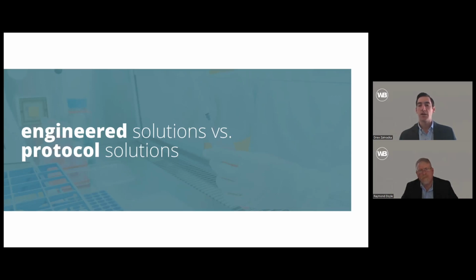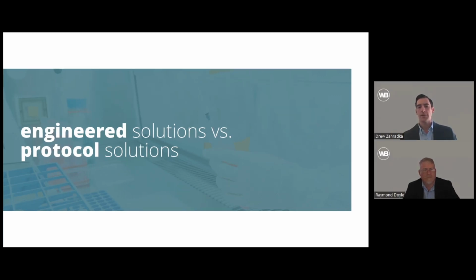So the engineered solution in this instance would have been to put in low wall returns, but low wall returns are not cheap. They require furring out the wall cavities so you can fit the duct, and it's more ductwork. Sometimes it has to be stainless steel duct, depending on what's being cleaned and what materials are used to clean down the space. So what the end user ended up doing was they put in a protocol so that people entering the space had to change their shoes and their socks before entering, to limit the amount of mold and fungal spores brought into the clean room.